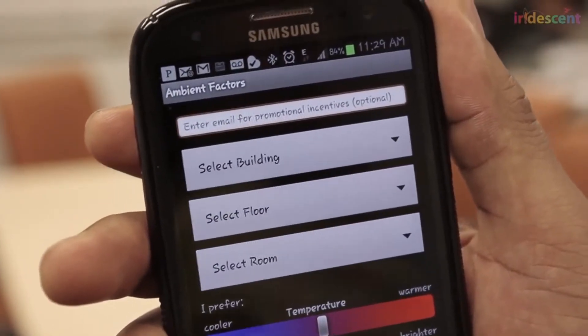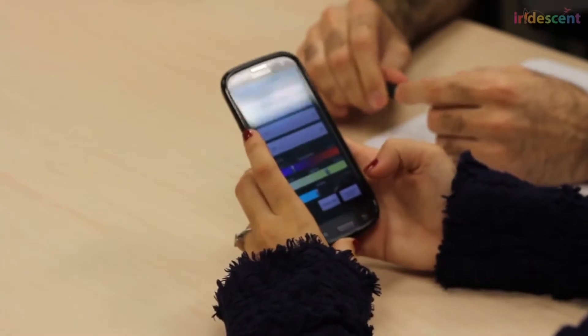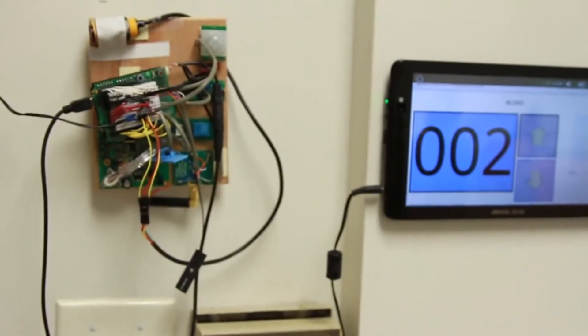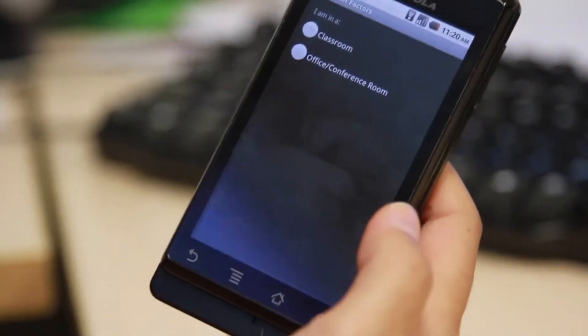I kept sending them responses about whether conditions were good or bad. By getting the occupant preferences and associating them with environmental variables such as temperature and humidity, we learn occupants' preference profiles over time, and then use a complementary controller on top of the existing HVAC system controller.